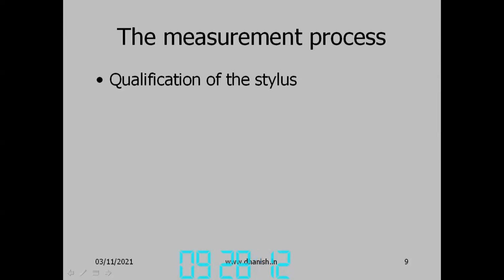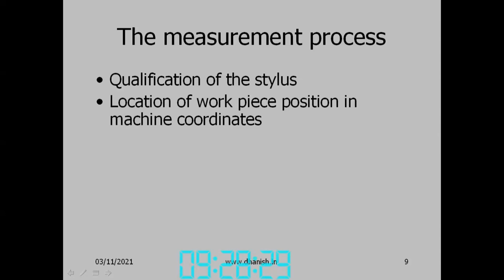We measure a known calibration sphere, and since we know the diameter of the sphere, we can calculate the diameter and the position of the stylus, and that is captured by the CMM. That's why the measurement process starts with stylus qualification. After that, we have to locate the workpiece position in machine coordinates. The machine coordinate system is always there. That is the reference scale, the coordinate system from which all the basic scales of the instrument are used for measurement. That will never change. Once you switch on, it will take up some zero, and that is not going to change.